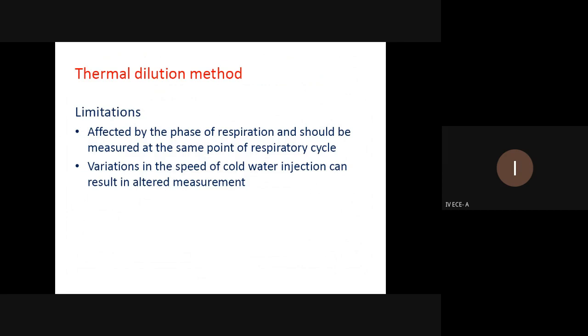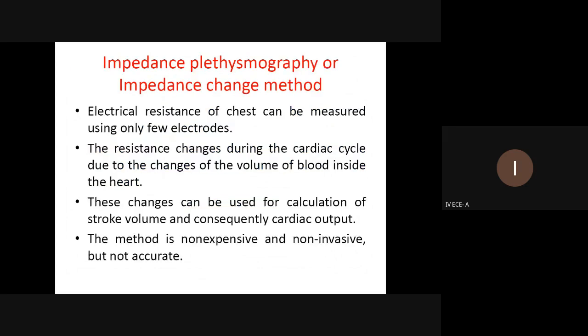Okay, so what are the limitations of the thermal dilution method? It is affected by the phase of respiration and should be measured at the same time of the respiratory cycle. Variations in the speed of cold water injection can result in altered measurement.